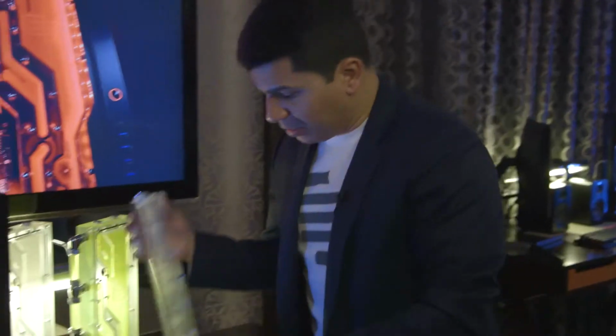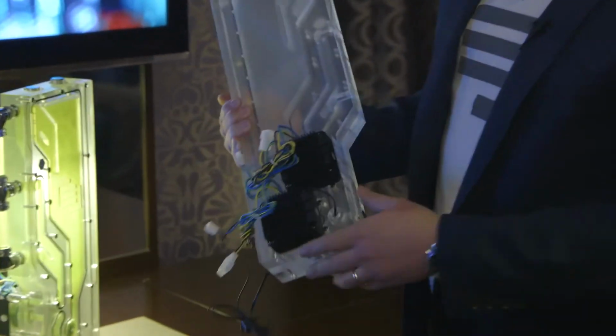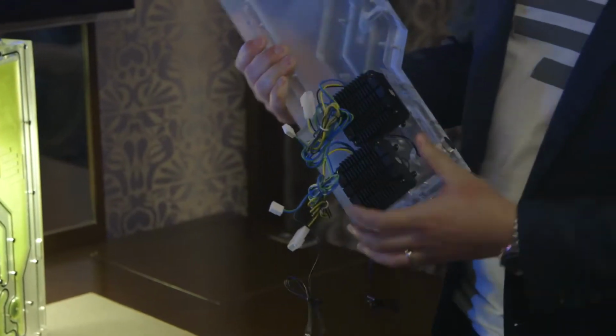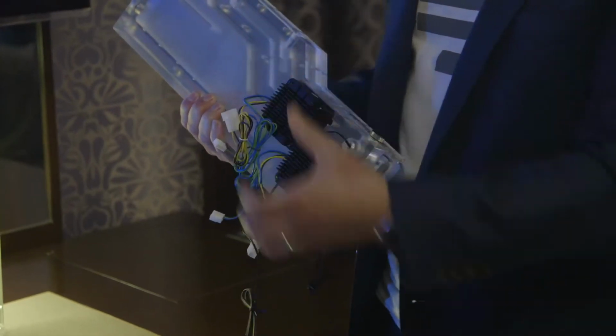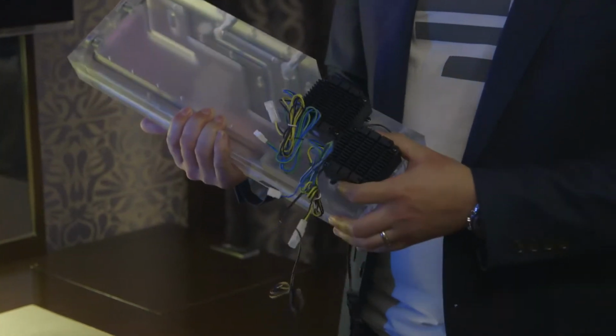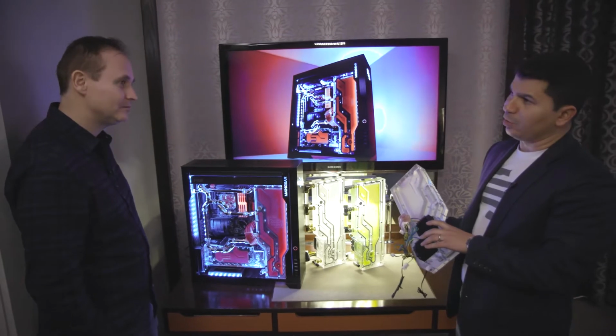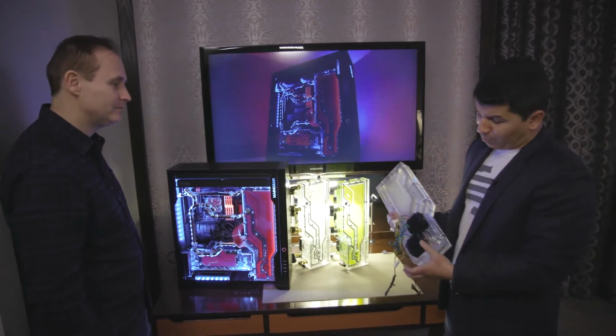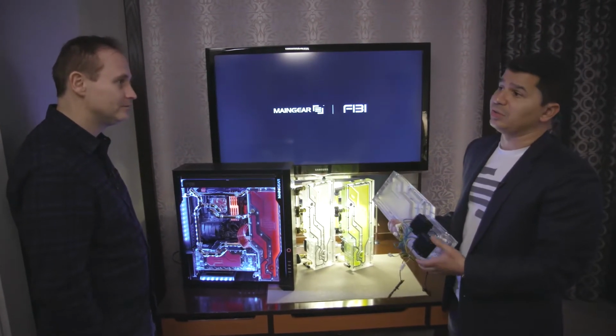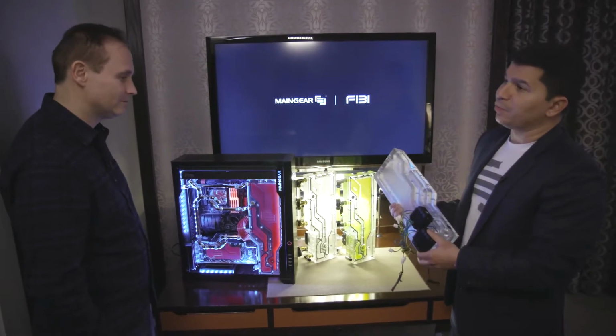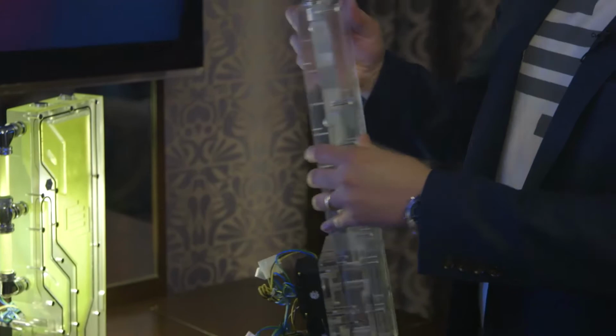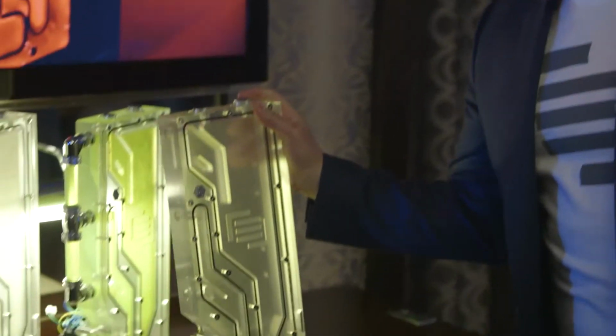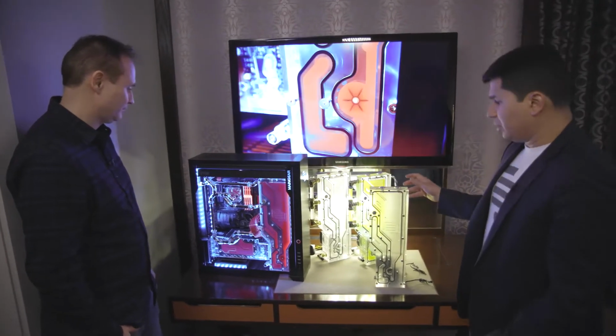Thank you. Part of it as well is we've integrated dual pumps behind here. It saves us some space in the chassis, and it also makes the system redundant, so we're able to run the pumps at lower speeds. If one pump does fail, you still have a fully functional system, so there's no downtime for you. There are temperature sensors and pressure release valves in this system as well. We're just making liquid cooling better.